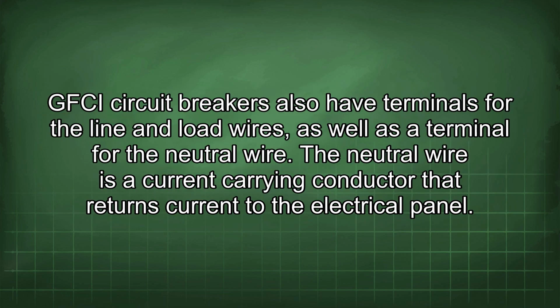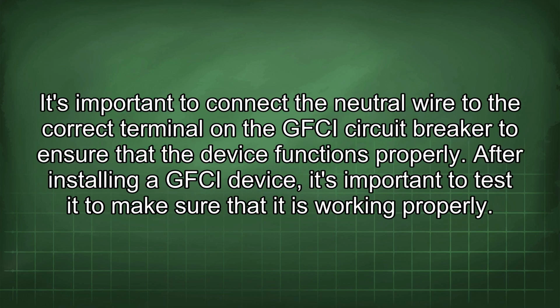GFCI circuit breakers also have terminals for the line and load wires, as well as a terminal for the neutral wire. The neutral wire is a current-carrying conductor that returns current to the electrical panel. It's important to connect the neutral wire to the correct terminal on the GFCI circuit breaker to ensure that the device functions properly.